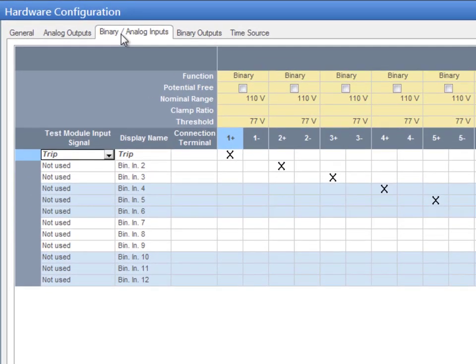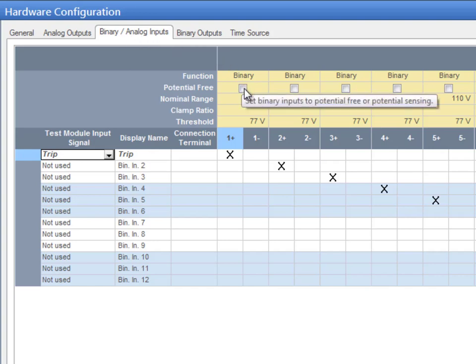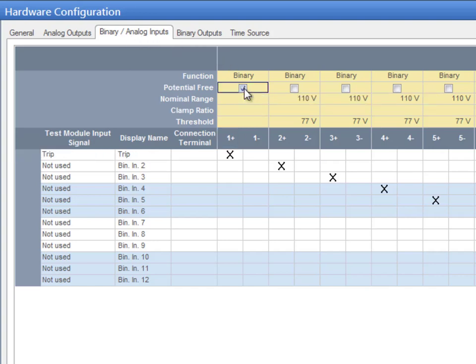Most importantly, do not forget to indicate whether the signal is connected potential-free, which means dry, or with a specific voltage, which means wet. If the potential-free checkbox is cleared, both nominal range and threshold fields become available.